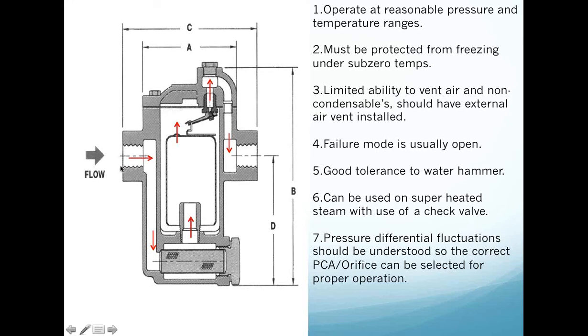And when I say that, the inlet pressure on the upstream side, if that's P1, and let's just say that my inlet pressure is 200 psig, I have a condensate return downstream pressure of 100 psig. If I take my 200 minus my 100, I have a differential pressure of 100 psig. So this trap, let's say, has the ability in my particular application to see 100 pounds of differential. These traps have different size orifices that give us the ability to pass different amounts of condensate in pounds per hour. We have to be intelligent enough to understand that the orifice is going to be chosen based on the differential pressure that we're going to see and based on the volume, or the amount, of condensate that needs to be processed.